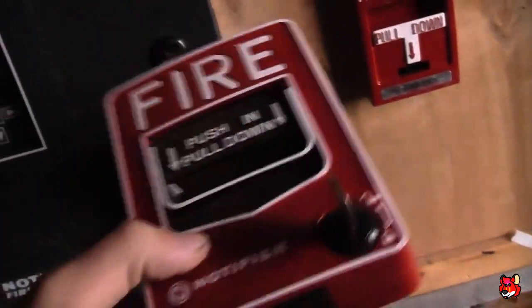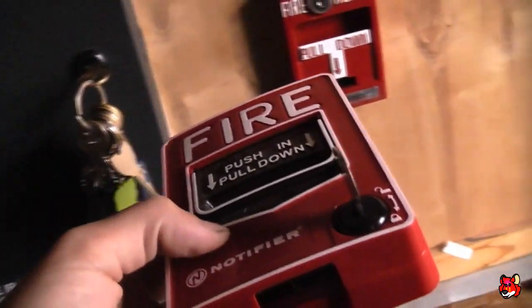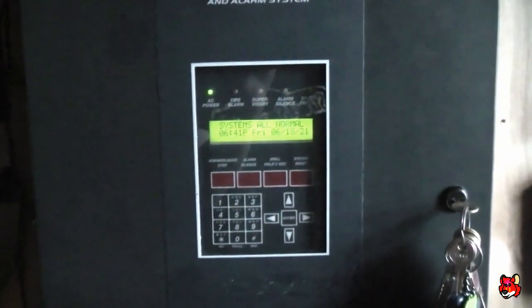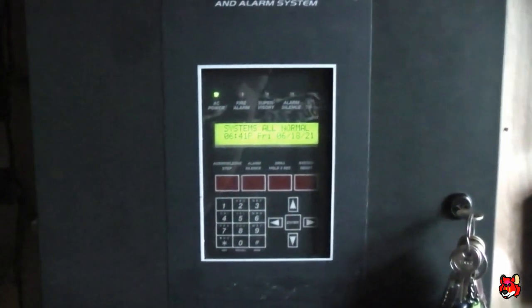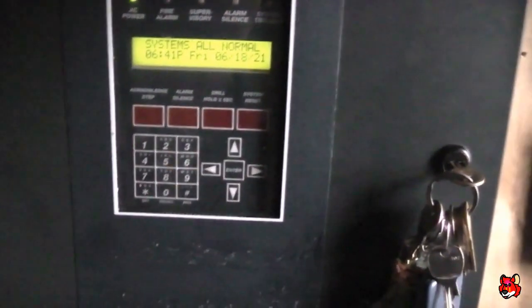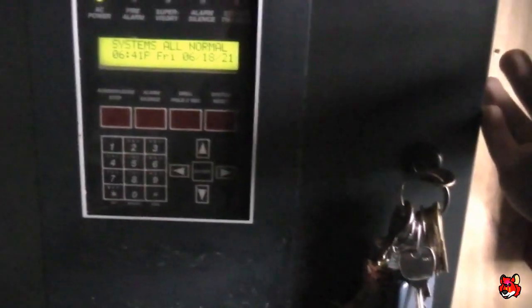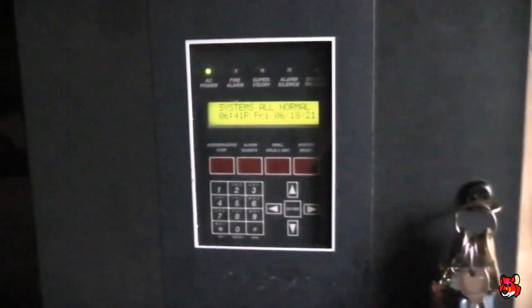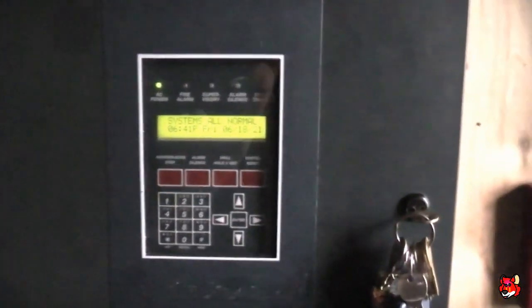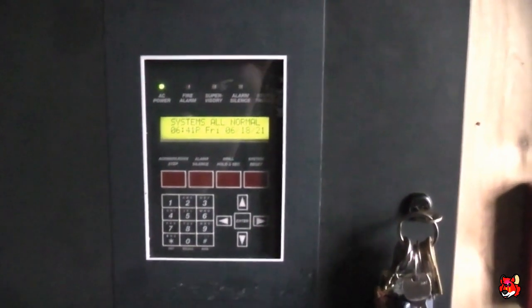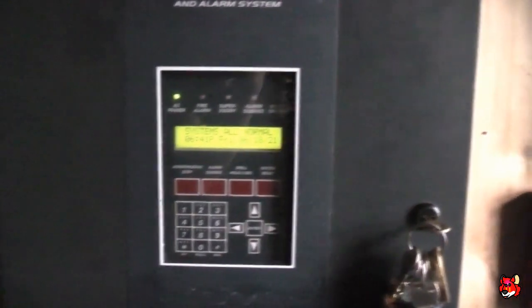However, as you saw in the videos, it obviously took the NBG-12LX. That's because this panel runs Notifier's older version of FlashScan or Notifier Clip. I've heard some people say FlashScan while others have said Clip. But it runs a Notifier protocol. And it pretty much detects OEM Notifier devices. So the NBG-12LX works with it and Fire-Lite does not. However, for some reason, I was able to hook up the module to my broken FCI-MS7 to this, and the panel took it just fine. I found that quite interesting.